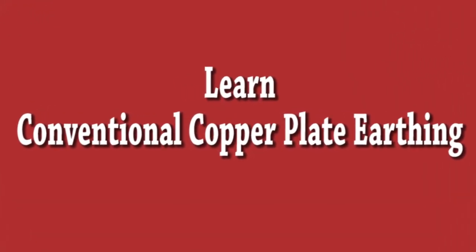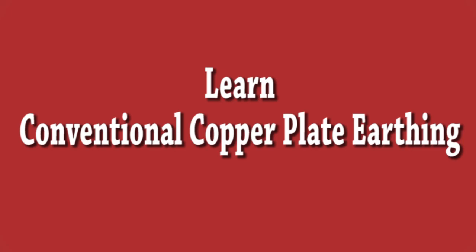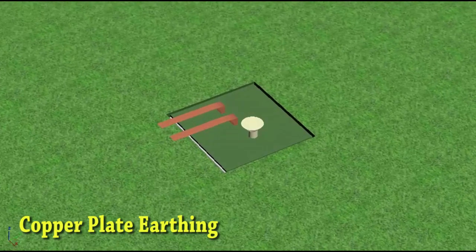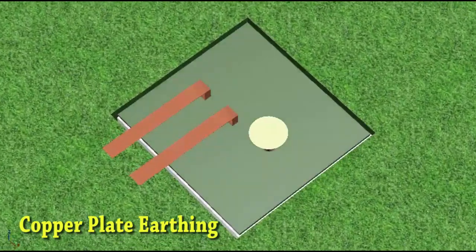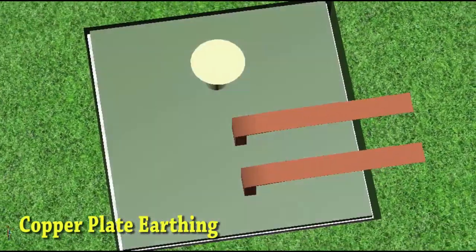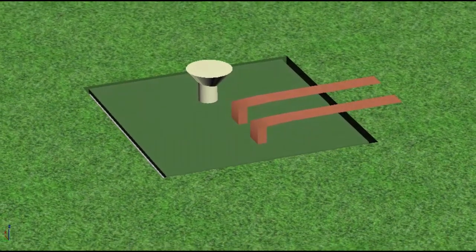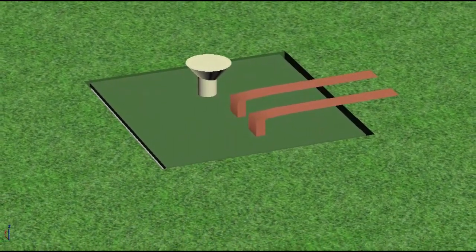Let us learn how to do copper plate earthing. Here we can see earthing with two strips, generally of galvanized iron, emerging from the earth pit. All earth wires are connected to these strips. Also, a funnel is there to pour water inside the earth pit.